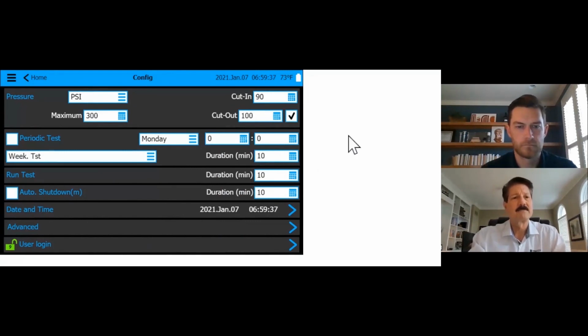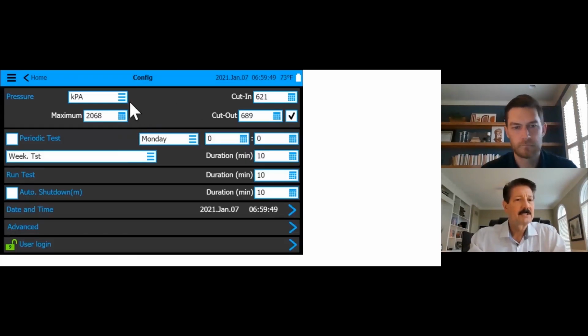How simple is this? Depending on what part of the world you're in, we could go from PSI, KPA, bar, MH20. Typically, the two I see are PSI and KPA. It's just a simple click of the button. But obviously in the US, it's PSI. Maximum 300 PSI. Well, the pressure transducer is actually rated higher than that. The pressure block is rated up to 500 PSI. But if you want to change this to widen your scale.